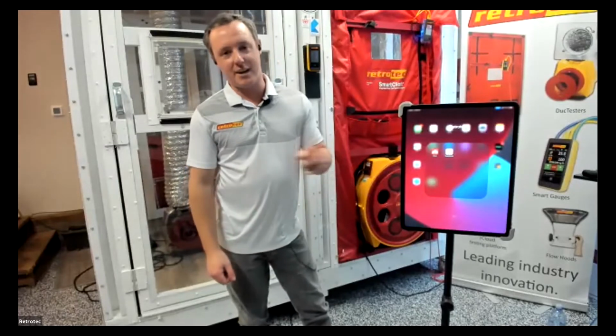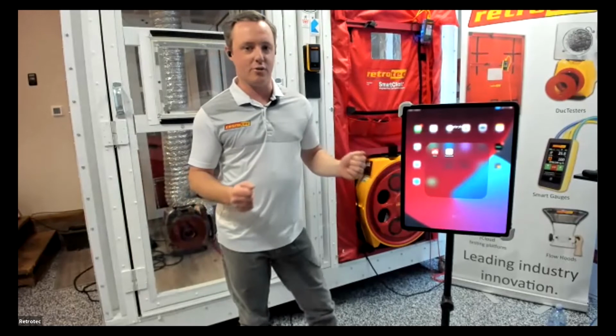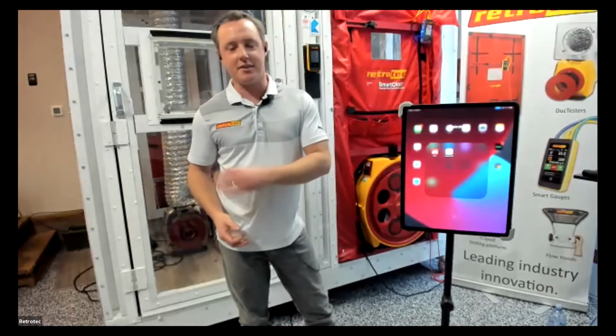I either missed something. A lot of times this happens. Sometimes there's some supplies in some sneaky spots, so you have to go back around the house and make sure you didn't miss a supply or a return somewhere. 9 times out of 10, that's what it is. You missed one. Or there might be a duct disconnected somewhere. So if you can't get to 25 with the fan running open, there's either a mistake that was made or there's a serious issue somewhere.